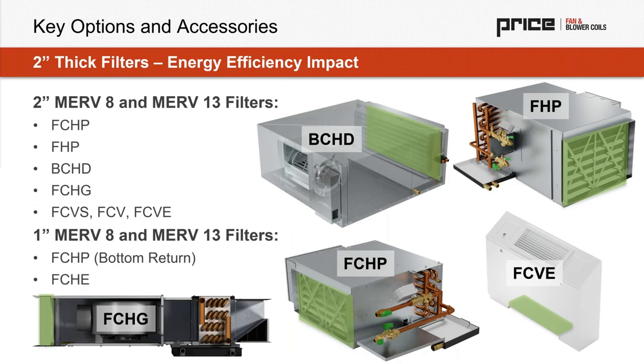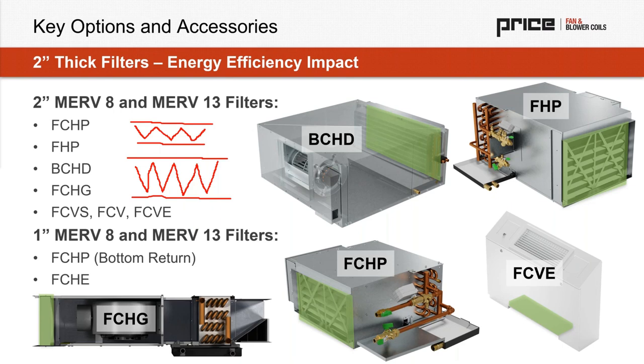Another thing I'd like to note is the filter selections and choices that we're using for our products. Something that was a little counterintuitive to me is that larger filter depths and thicknesses actually result in lower pressure drop. That's because these filters are pleated. If we look at pleats with a 1-inch thickness versus a deeper pleat for a 2-inch thickness, and apologies for my scribbling on screen, but it helps to communicate it, the effective surface area of a thicker option is much larger as well. So the thicker the filter, the lower the pressure drop.